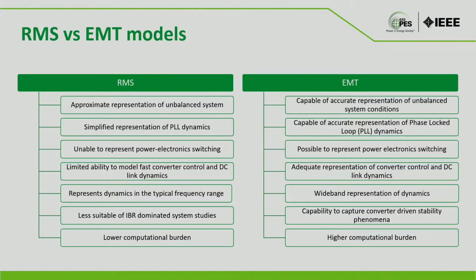RMS is normally less suitable for IBR dominated power system studies. If you've got like 1 or 2 IBRs, you're probably okay, not necessarily fine, but should be okay. But if you've got a grid with a lot of IBR percentage, a lot of renewables in the grid, then you probably need to think about going beyond RMS model and start looking at EMT model, particularly with a grid having high penetration of inverter-based resources.